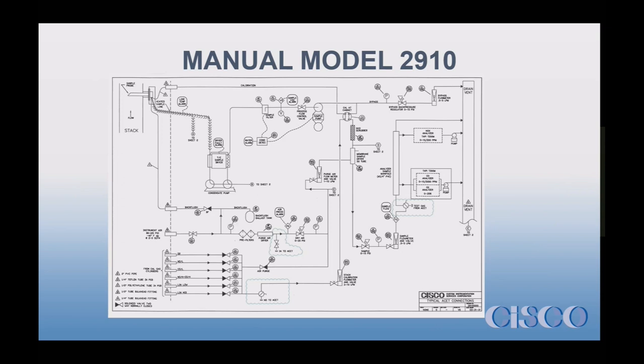That's the three-way valve that would reroute your NO span gas from the system up to the CE tester. There's just a T with an off valve here, and that can be downstream with a pressure regulator if you want the upstream. And then, of course, there's this valve here that routes the sample from the tester into the manifold. So the modifications to a system, if you wanted to use it on a continuing basis, is pretty simple. Okay.